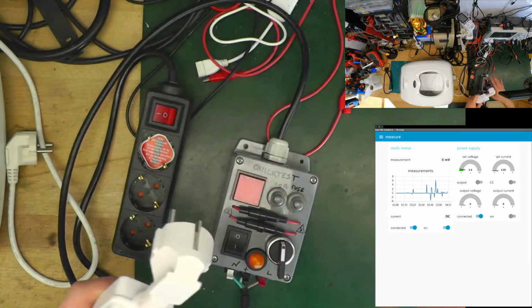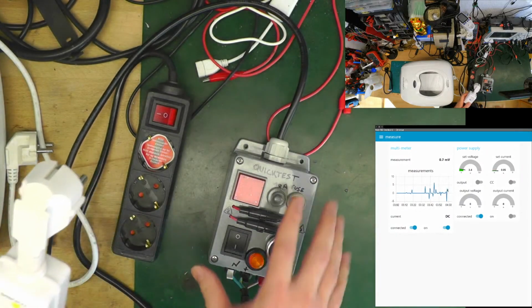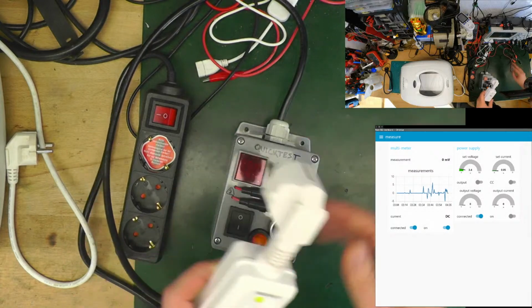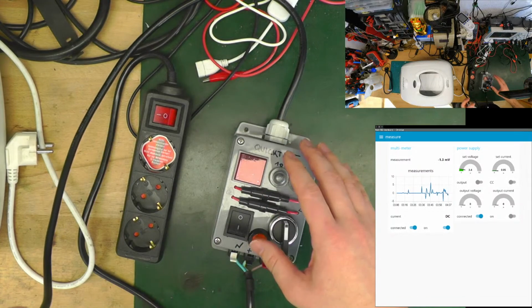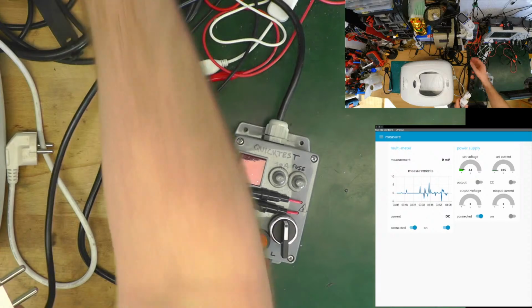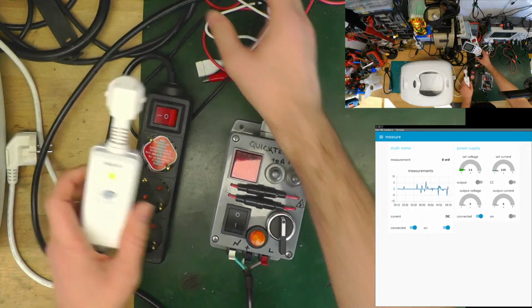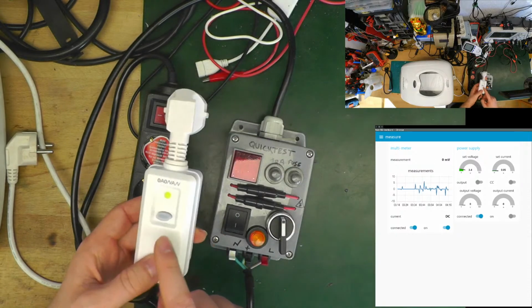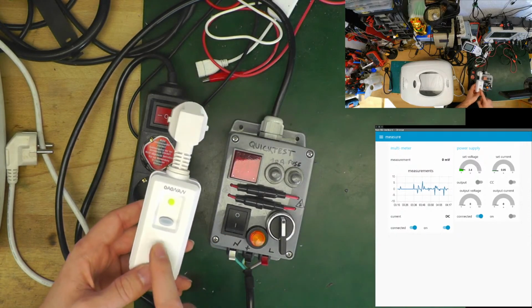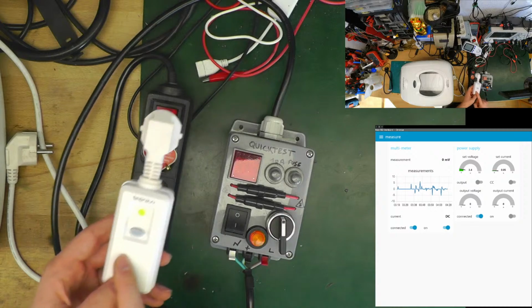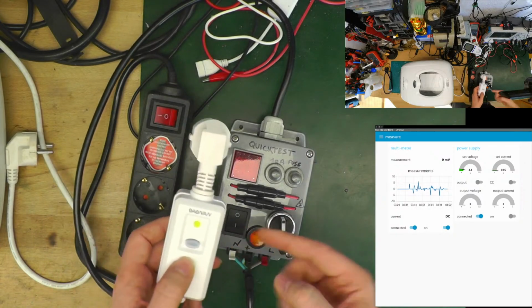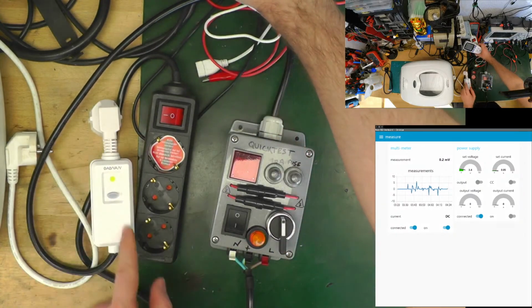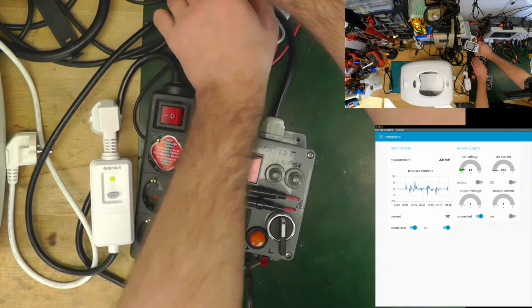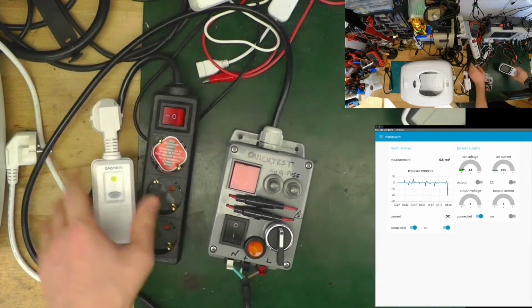So the 10 milliamps is a bit less than the 30 milliamps I have in my electric cabinet, which blows the fuse. The 10 milliamp doesn't mean it will trip earlier - it means it trips with less current. Generally, with less current, it trips earlier. So I have a 30 milliamp in the power box which trips, and this is a 10 milliamps.